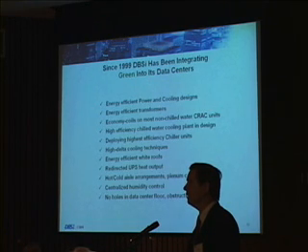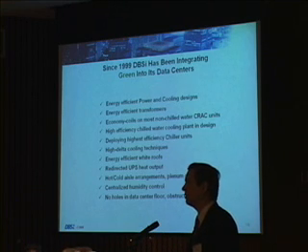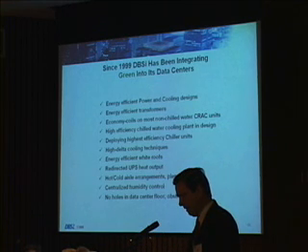In the summertime, a typical roof is running at almost 200 degrees to the touch. With a white roof, it runs 10 degrees above the outside air temperature. So if it's 90 degrees outside, that roof is only 100 degrees and not 200, and that thermal barrier is coming into your data center, making your CRAC units work harder.